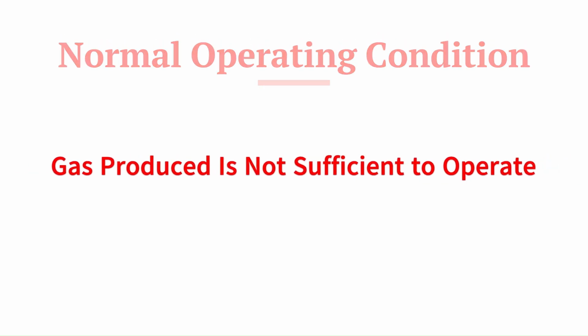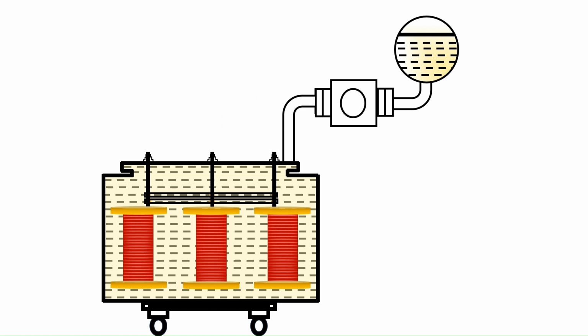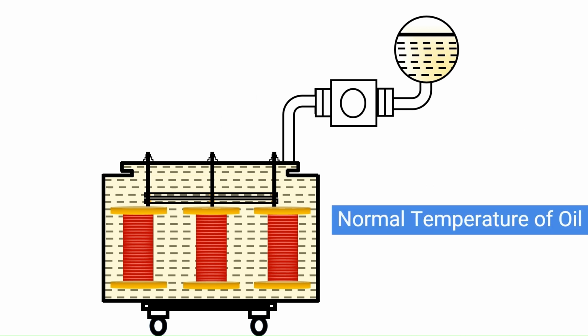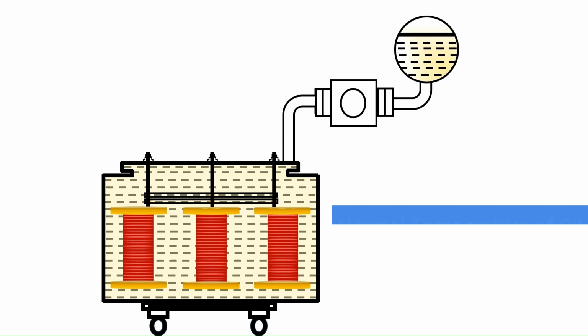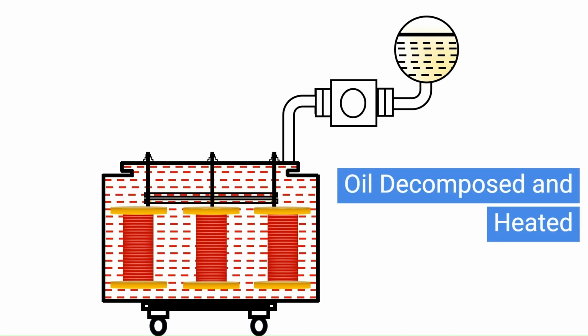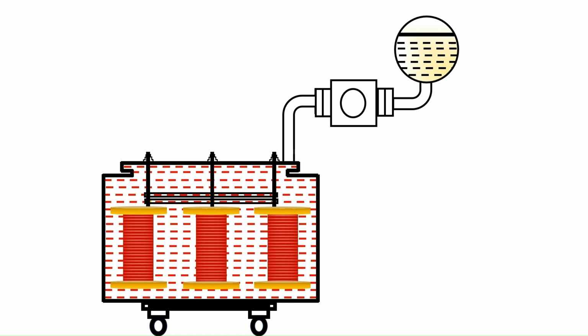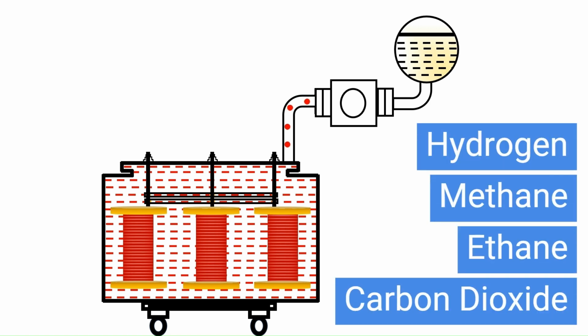Now we will see working of Buchholz relay. At the time of normal operating condition, temperature of the oil is also normal and therefore gas produced by the transformer oil is not sufficient to operate the relay. Now suppose an incipient fault occurs in the transformer. Due to the fault, oil will get decomposed and heated. So it will produce gases like hydrogen, methane, ethane and carbon dioxide. The gases produced are lighter than air. Therefore, they will move upward and enter the upper portion of the Buchholz relay.